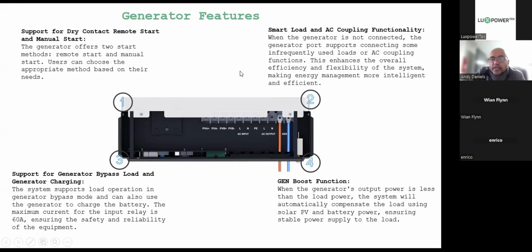And in number 2, we're going to talk about smart load and AC coupling functionality. This is a very cool feature for the SNA. Smart load simply means that if you are not using the generator port to feed the generator in, you can allocate it to a smart load output port. It means that when the generator is not connected, you can turn that generator port into an auxiliary port. So on the settings page, you will see smart load settings. You tell it when there's sufficient solar and when there's sufficient battery SOC. You give it the flags on when to start, when to stop. If it's load shedding and there's solar and there's enough battery, it will put out power on the AC power output here, as well as the generator output as an auxiliary output.